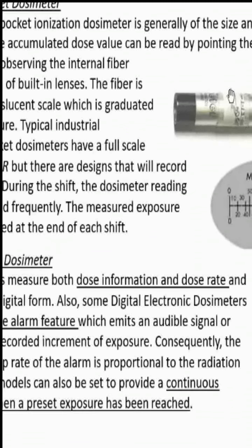Immediately you get a value of the amount of radiation you have taken. This pen is not to be reset once you are on site. You make it zero, start using it for a few days and note the readings every day. Once it goes beyond the allowed limit, you stop going to the site.